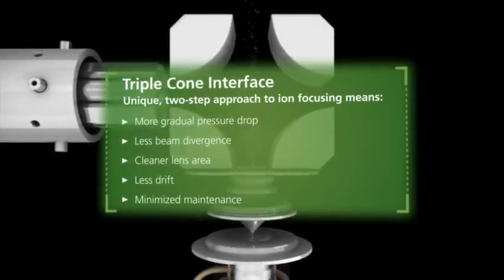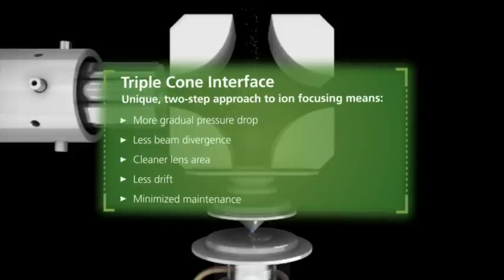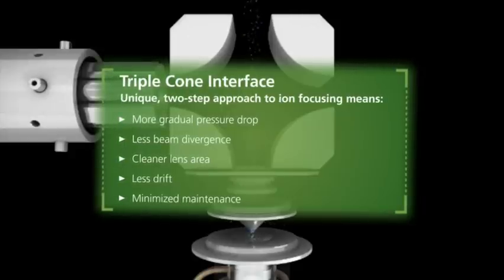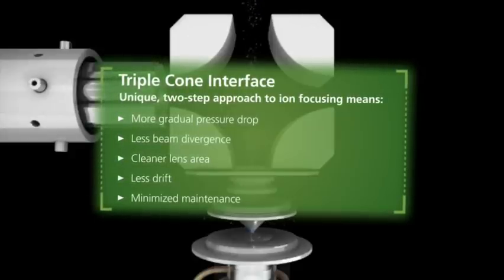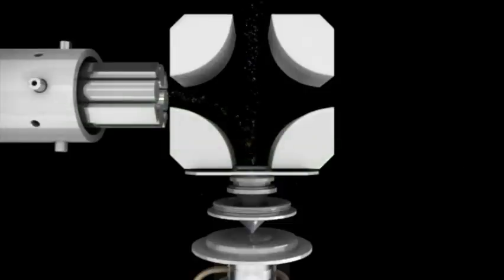Together, the triple-cone interface and quadrupole ion deflector eliminate the need for routine operator maintenance inside the vacuum chamber and prevent the universal cell from ever requiring cleaning or replacement.